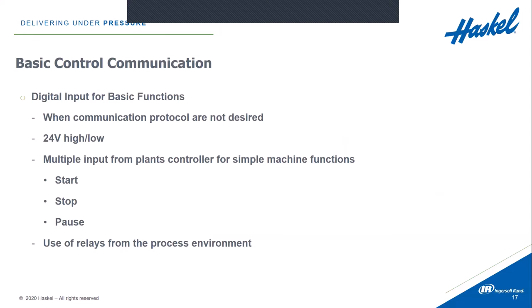If advanced communication protocols aren't present in your plant already, you can use just 24-volt high-side signaling with relays. This is already pre-built into the Q-Drive. You won't have your full advanced features where you would send specific tag values from all your IO in the system, but you could at least use existing automation in your plant and use relays or 24-volt high-side signaling to do simple machine functions like start, stop, and pause. For example, when you're ready to start boosting gas, you could just send a simple signal and have the Q-Drive start up and start pumping gas for you.